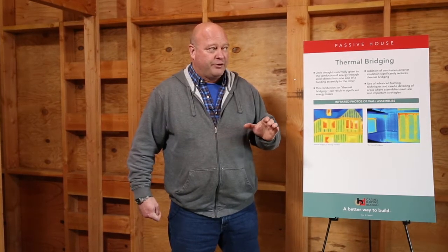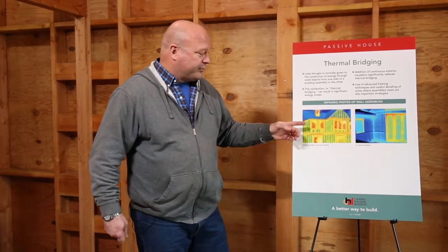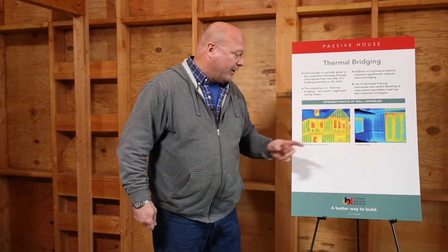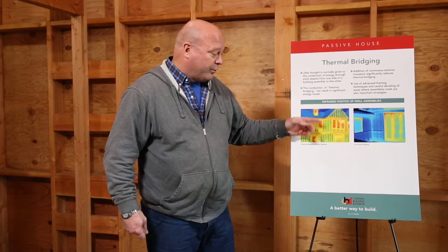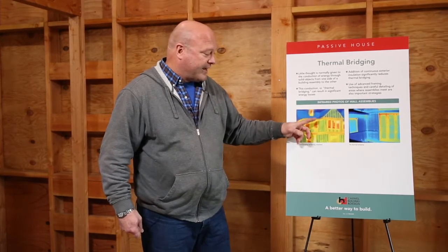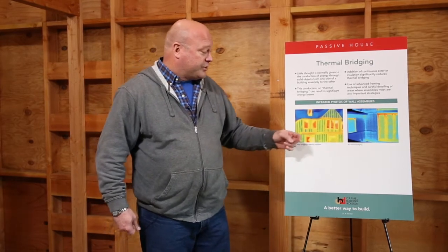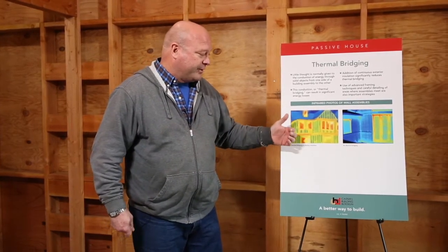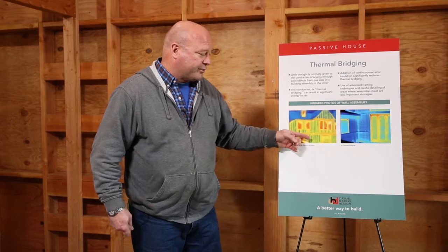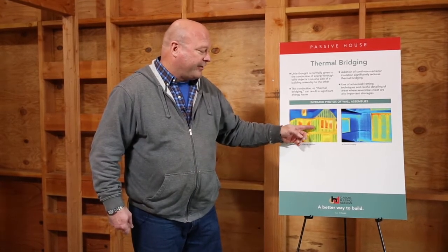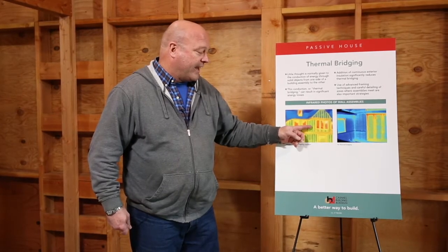After you've made sure that you haven't made any big mistakes like that, then we get down to smaller thermal bridges. So this image here actually shows a conventionally built house, and you can see it's a thermal image, and you can see all these lines where you can actually see the studs. And what that represents is that the energy and the heat, this is a thermal image, so we're measuring the surface temperature. These areas are slightly hotter than the adjacent areas where we have the insulation.